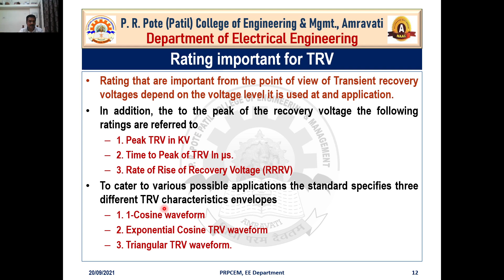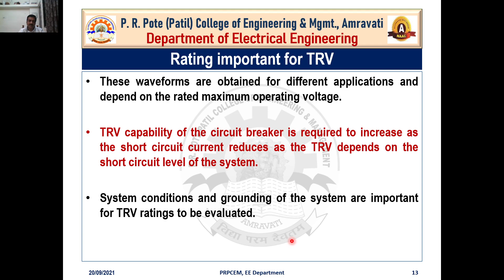Here the TRV capability, that is the transient recovery voltage capability of a circuit breaker, is required to increase as the short circuit current reduces, as the TRV depends on the short circuit level of the system. So what is the capability of a circuit breaker? What it can withstand mechanically also totally depends on what kind of short circuit current it has inside it. So we require to improve the TRV capability of a circuit breaker, and that totally depends on the short circuit level of the system, that is, the maximum short circuit current being handled by your circuit breaker. System conditions and groundings of the systems are also very important for TRV ratings. So what are the system conditions and what grounding solutions do you have? If you have proper grounding, then you can reduce the TRV effect inside the circuit breakers.